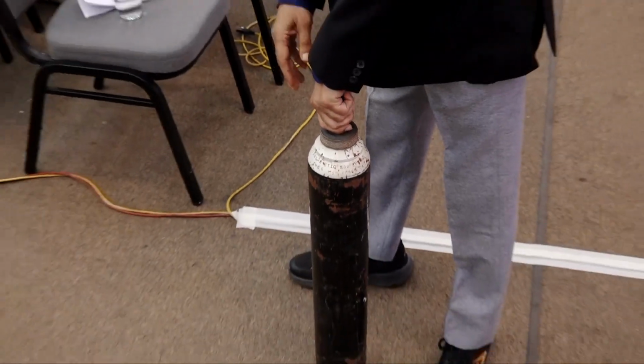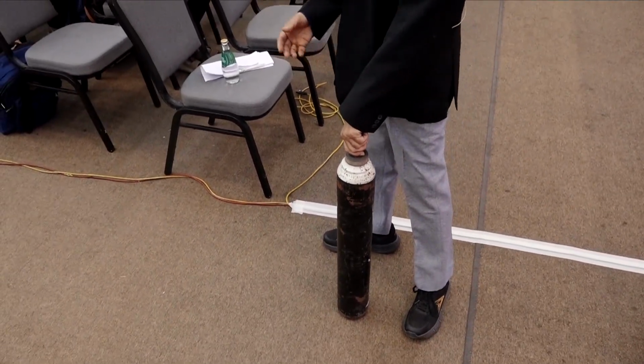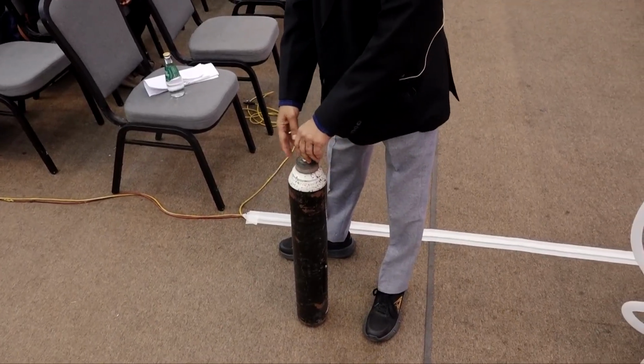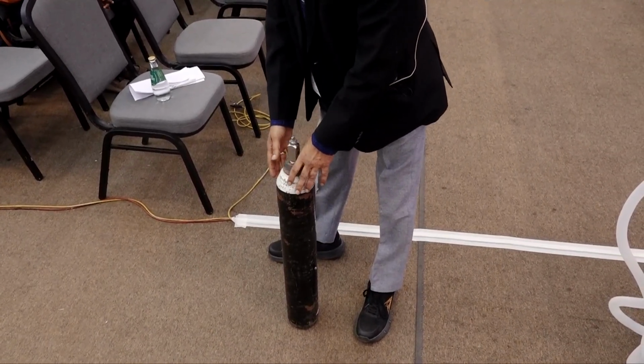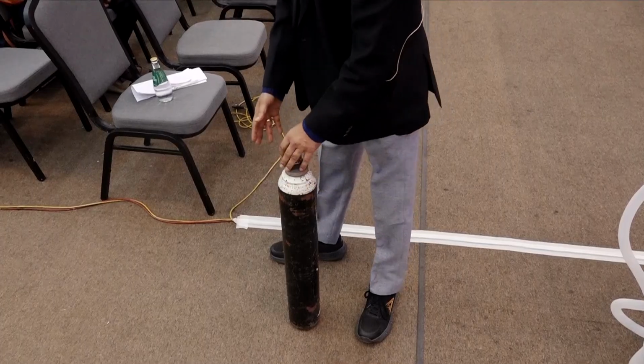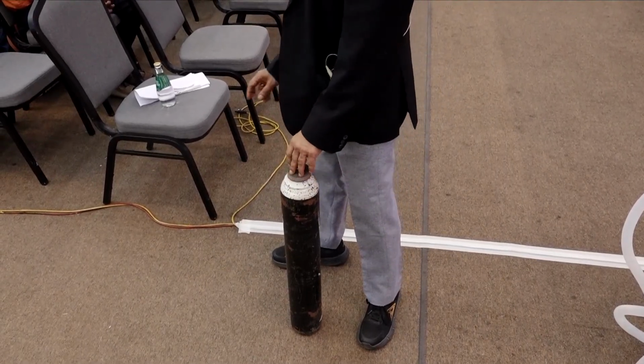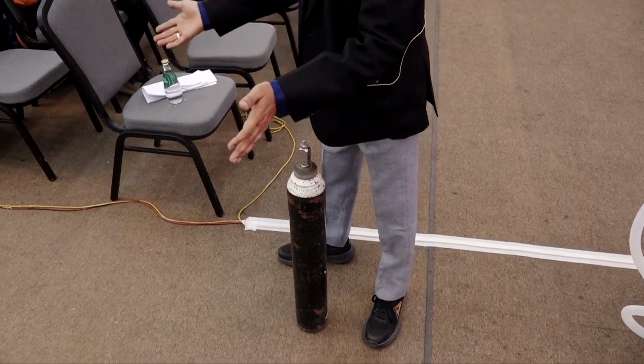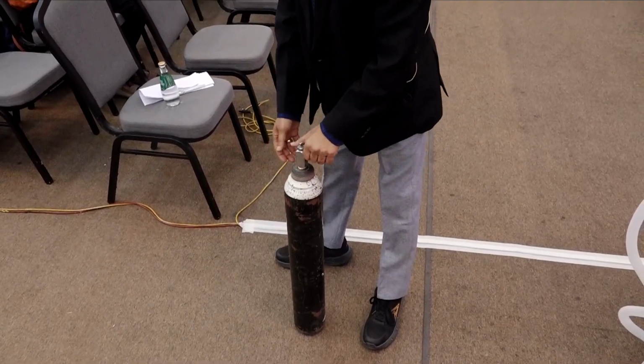Second thing is it can hold more oxygen and nitrous oxide, almost 20% more. So that is the advantage, one safety feature. Another safety feature is there are no joints. These cylinders are made seamless. No joints, because with high pressure gases, if there is a joint, it would open up. So that is another safety feature.